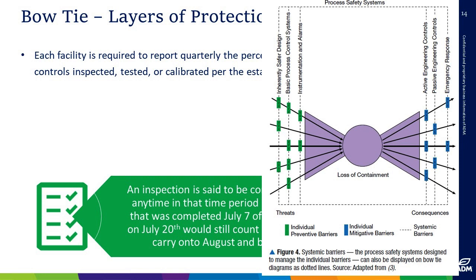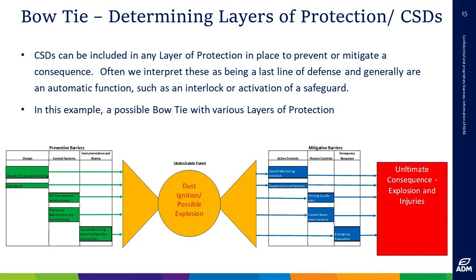So do we understand what could go wrong? Are we tolerating that risk? What are our critical safety devices in this process? Have we identified them? In this case, maybe you have something similar—I don't know if you've thought about it—is that high-level indicator on that tank critical? Is that bonding wire that prevents the pump from running when you're moving flammable liquids critical? Again, it goes back to your tolerance, it goes back to what you think. For me, yes.